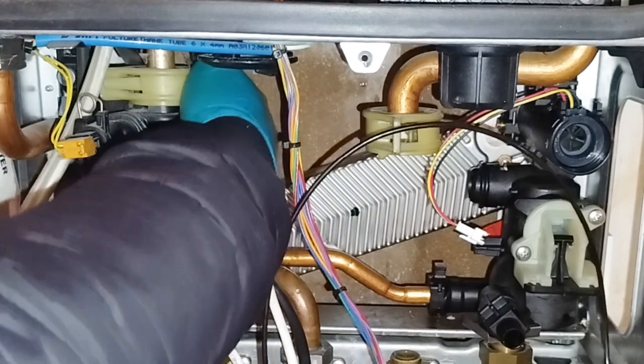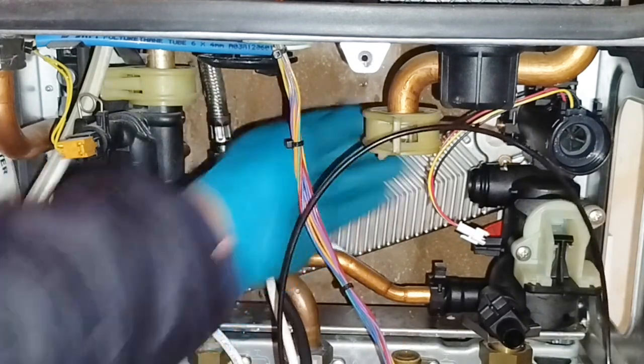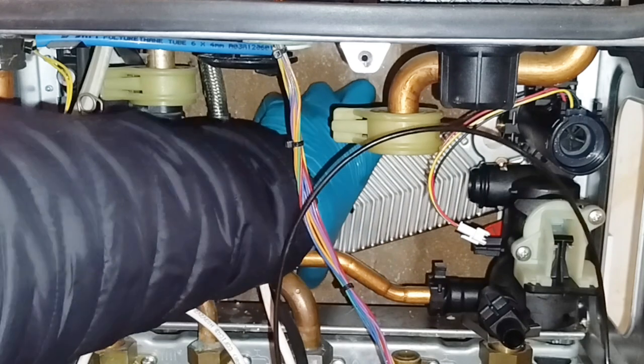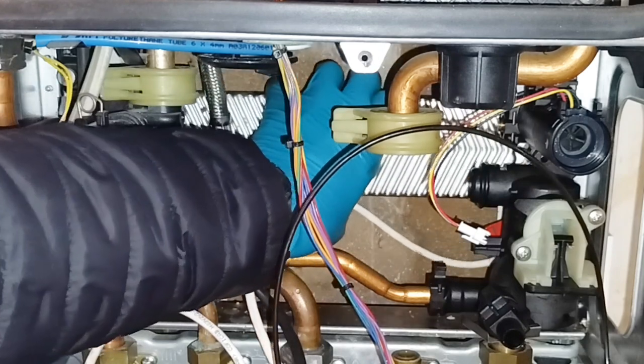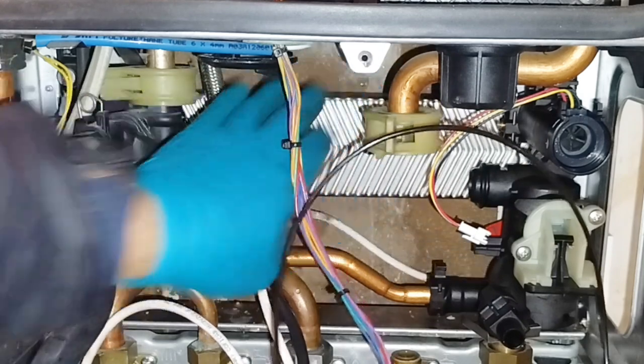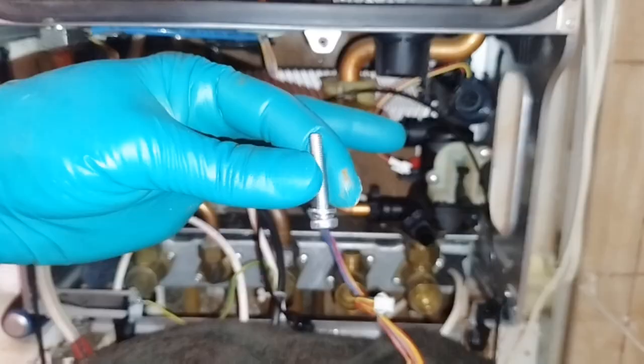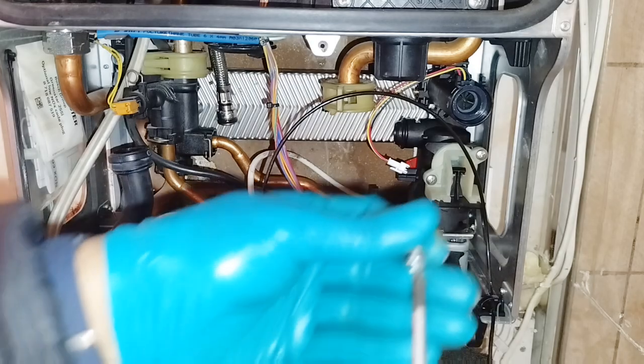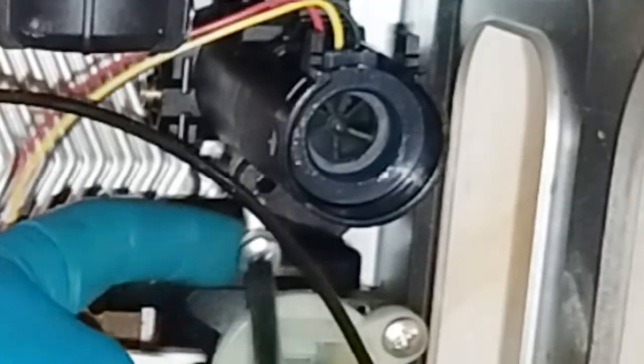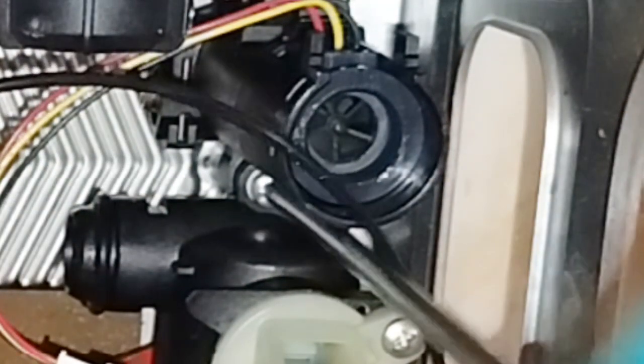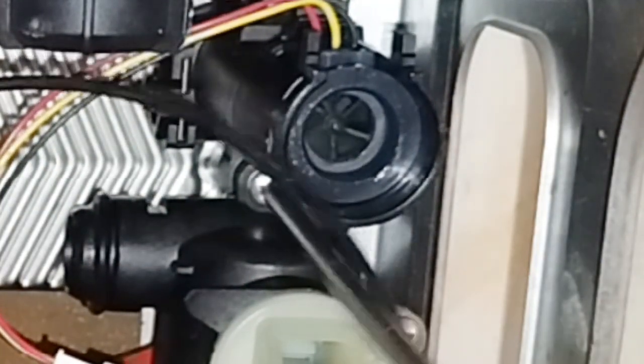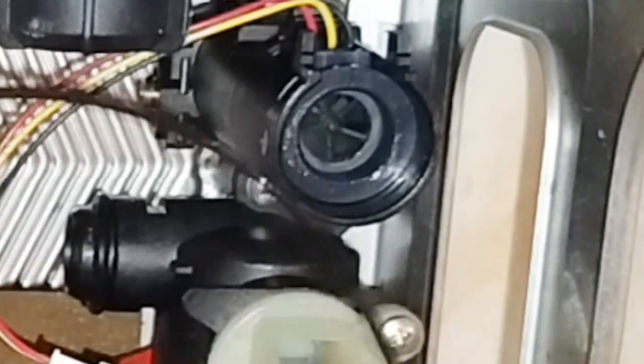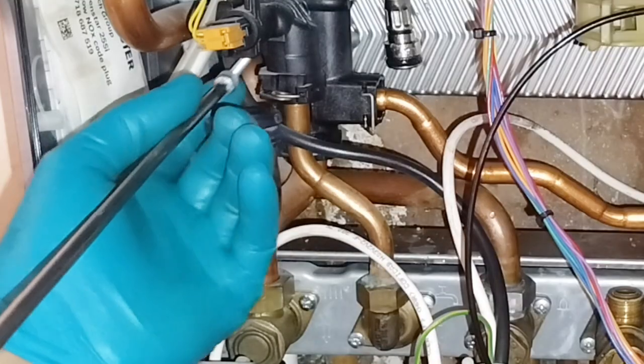So I've checked both left and right hand side behind the flow and return manifolds to make sure that the O-rings, the seals for the plate exchanger, are still in place. This is the screw which is going to hold the plate heat exchanger in position. All right, so we will tighten it in at this point, so the plate heat exchanger is left in position and it's completely tightened. We will then put the screw on the left hand side, the flow manifold as well.